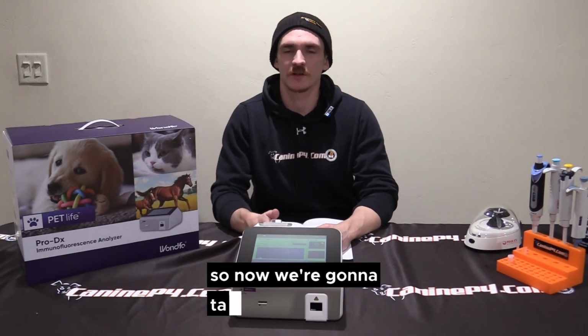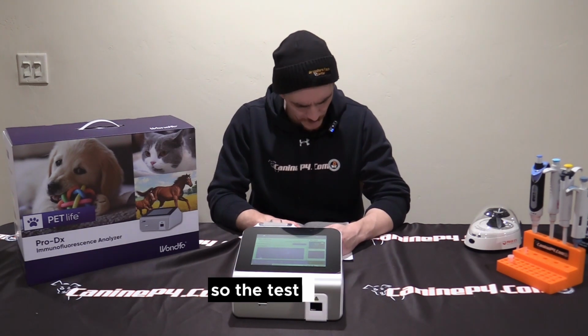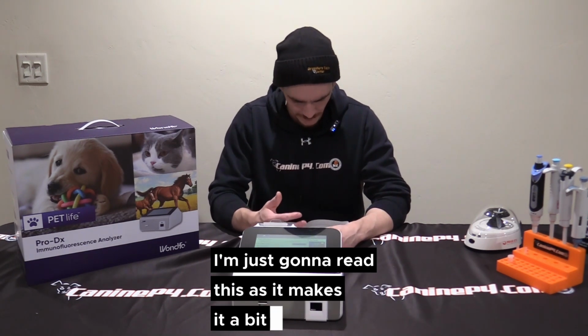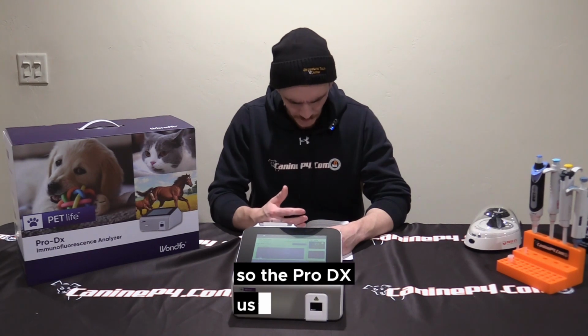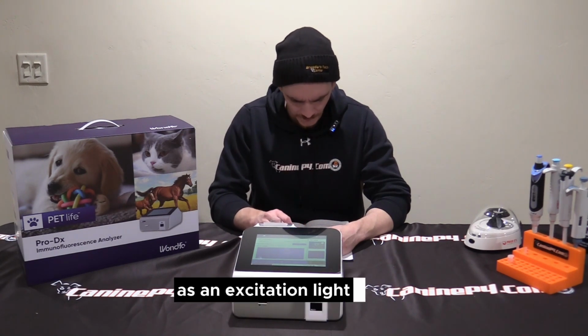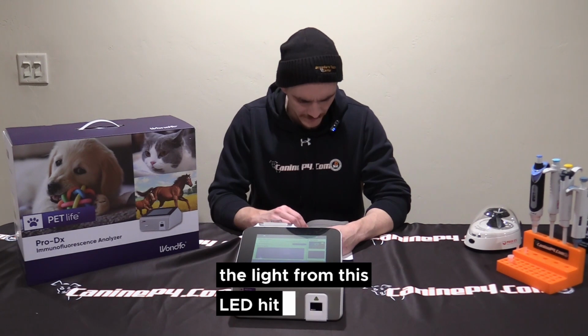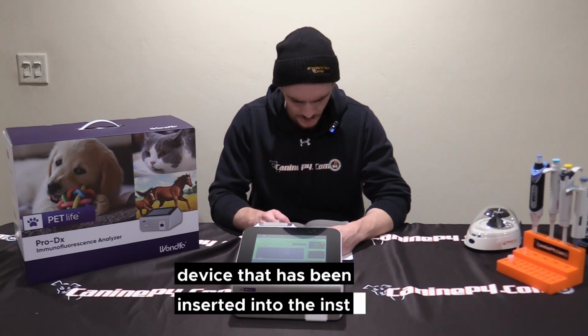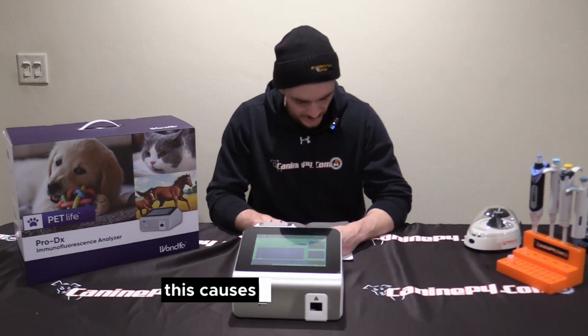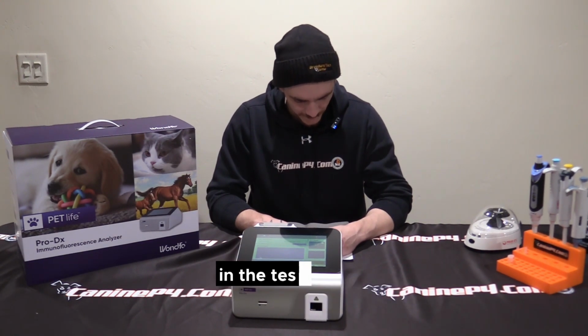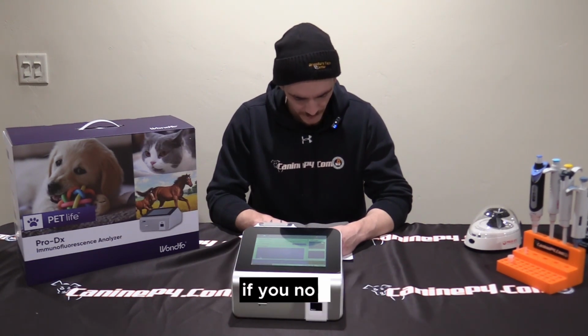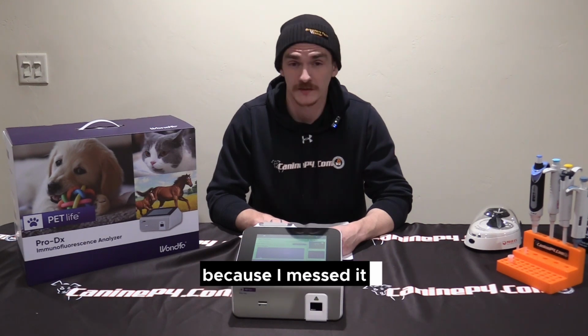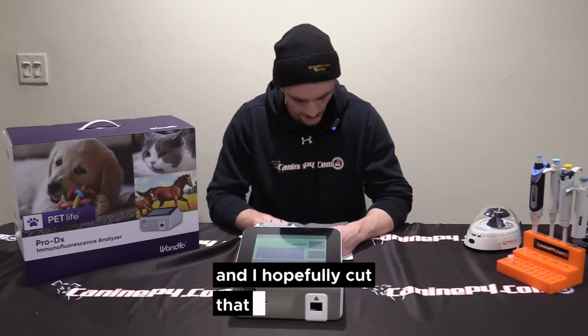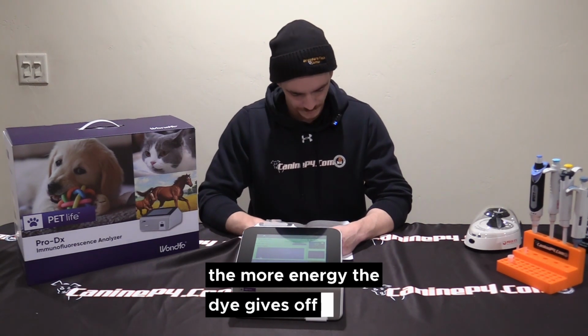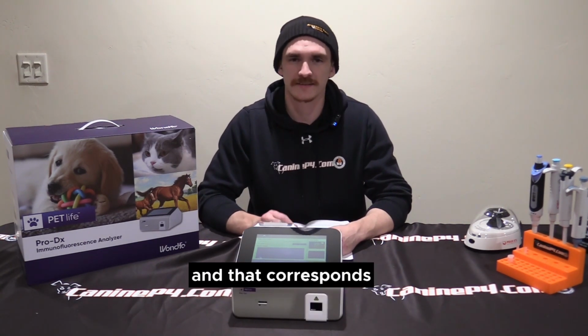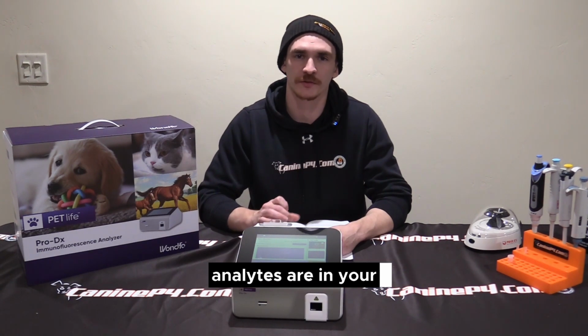So now we're going to talk about how it works. So the test principle, bear with me, I'm just going to read this as it makes it a bit easier. The Pro DX uses an LED as an excitation light source. The light from this LED hits a test device that has been inserted into the instrument, which is the test kit. This causes the fluorescent dye in the test device to give off energy. The more energy the dye gives off, the stronger the signal. And that corresponds to how many progesterone analytes are in your serum sample.